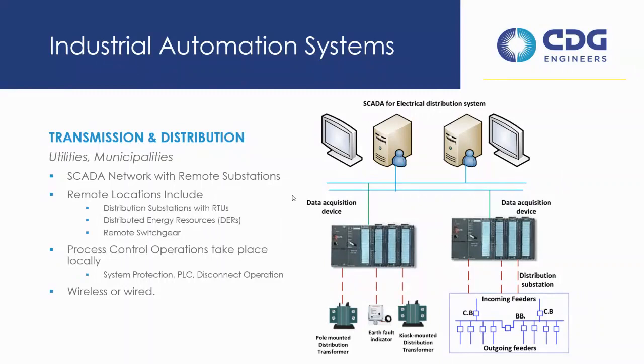You can also take in some process control operations. So if you have like a PLC at a remote substation or remote pump station, or you have a lift station of some sort, you need to know what's going on with that PLC, you can take that back easily via SCADA and monitor what's going on. CDG can help out quite a bit on the T&D side of things, and SCADA type networks. That's what our utility services group is around for. So they can take any kind of master terminal unit and RTUs type system at a substation or a distribution type location and take it back to a main central location and all the communications in between, set up the network. All that our utility services department can do.